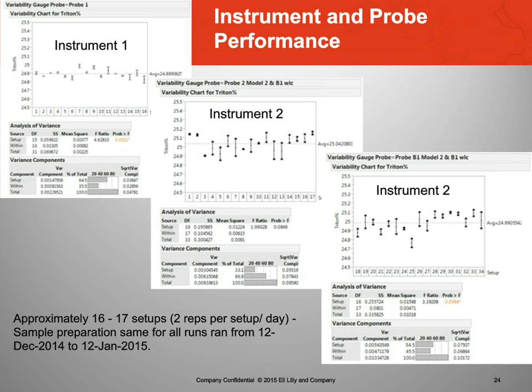So I also just went, for the sake of comparison, this is historical data on instrument 1. The intermediate precision over the course of a year was around 0.4, which is quite good. Again, I'm a little bit tighter than the limits, but none of the data failed. The point of this slide is to show performance over a year's period of time. And the fact that we did a model adjustment, and by changing the pre-processing, we tightened up the variability of the method.